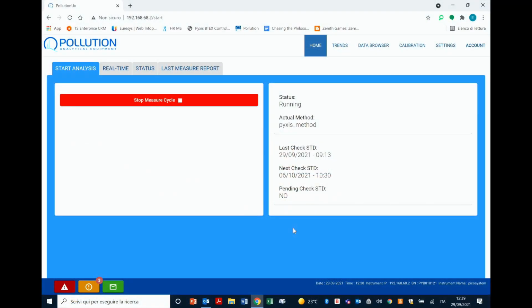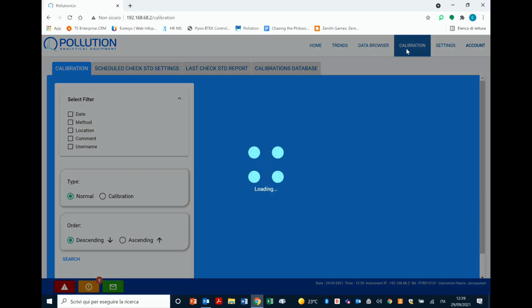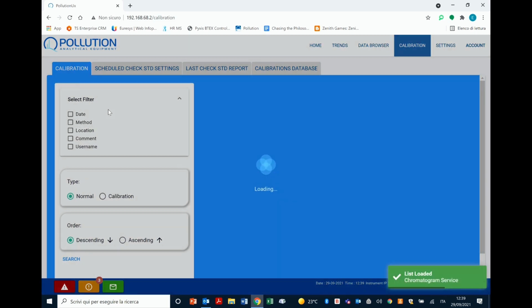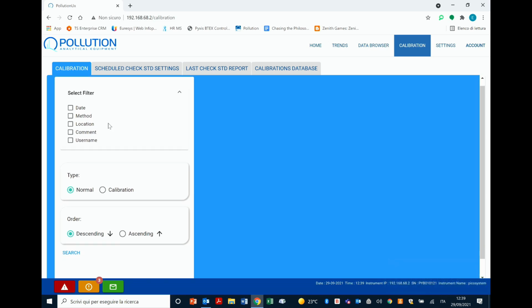Okay, so we are here in the home page of the instrument. You can see here the actual method that is loaded. So basically you will calibrate only the method that is now loaded and running. Also, to calibrate, you need to stop the measuring cycle and the instrument must be on status ready. So you go in calibration, and here this window will pop up.